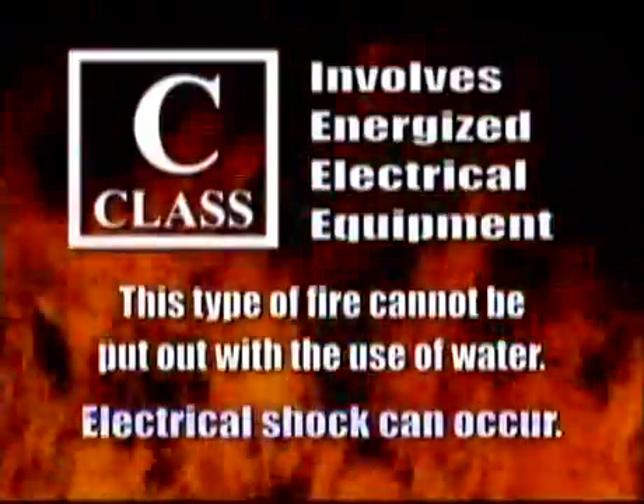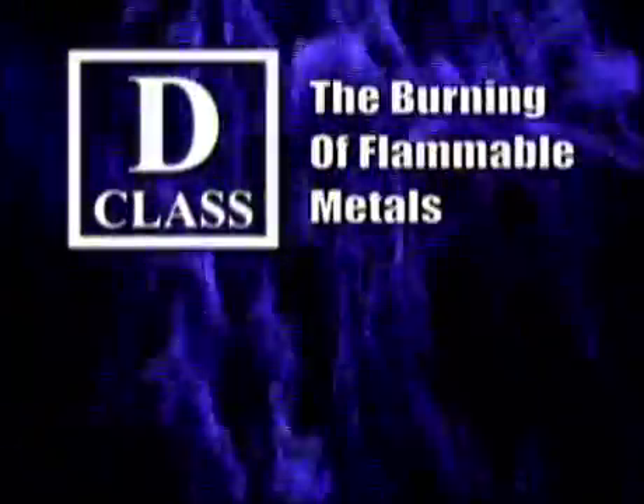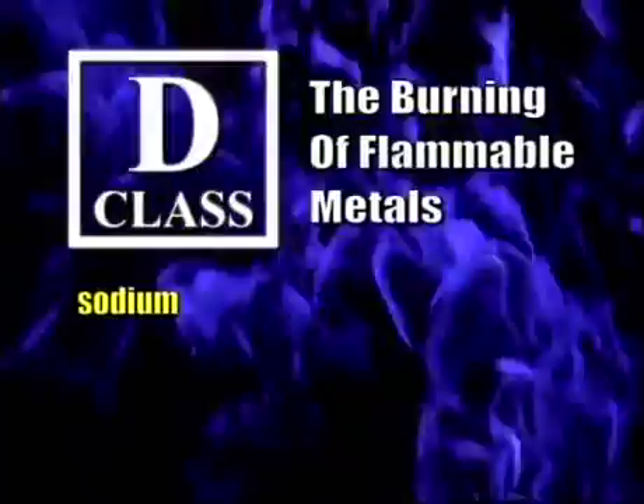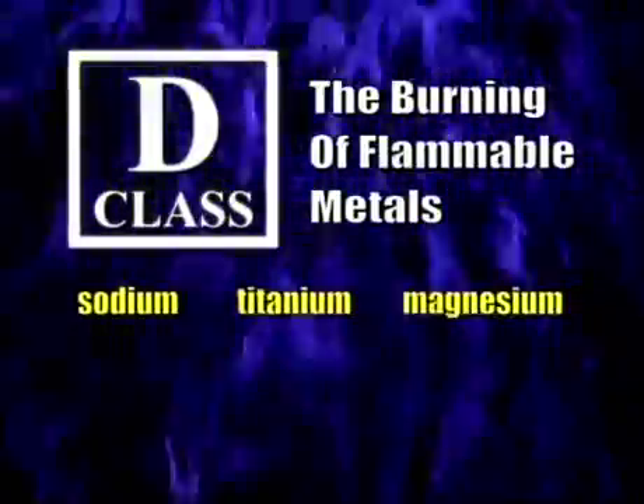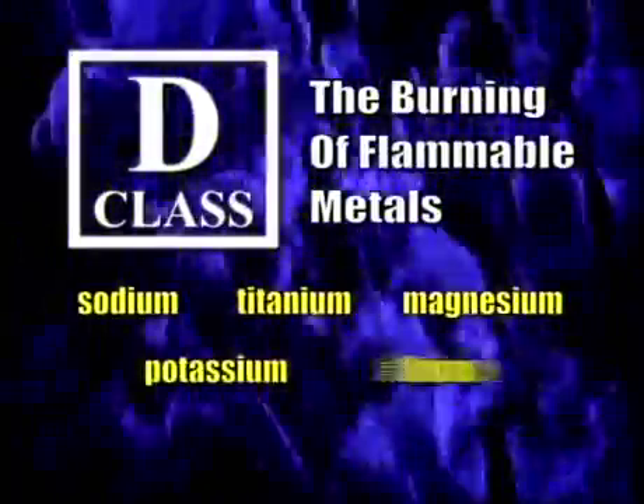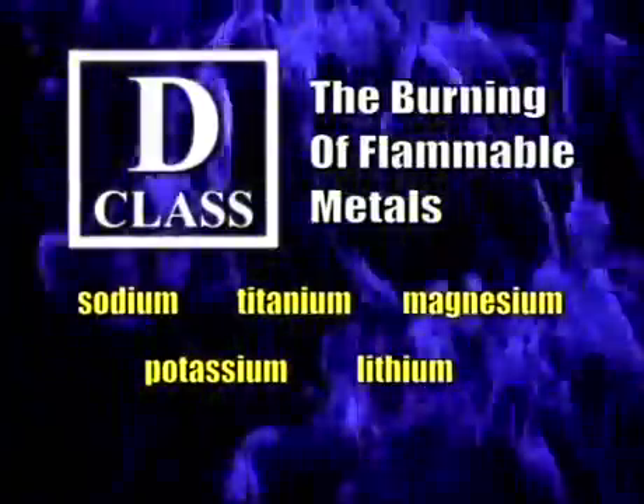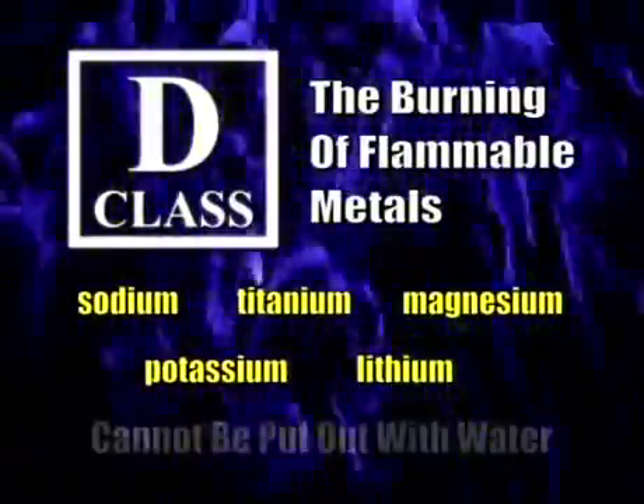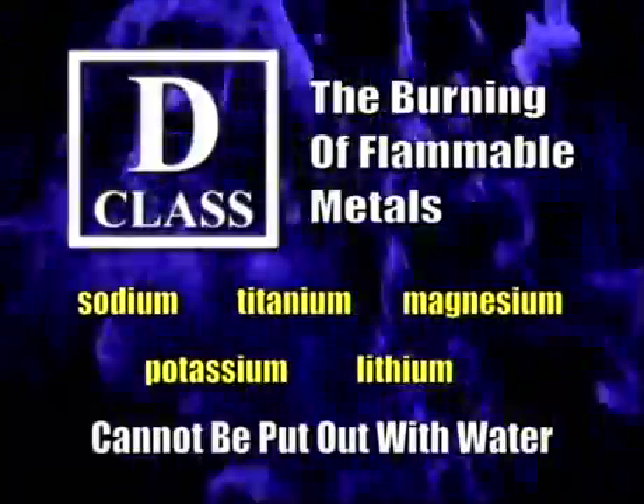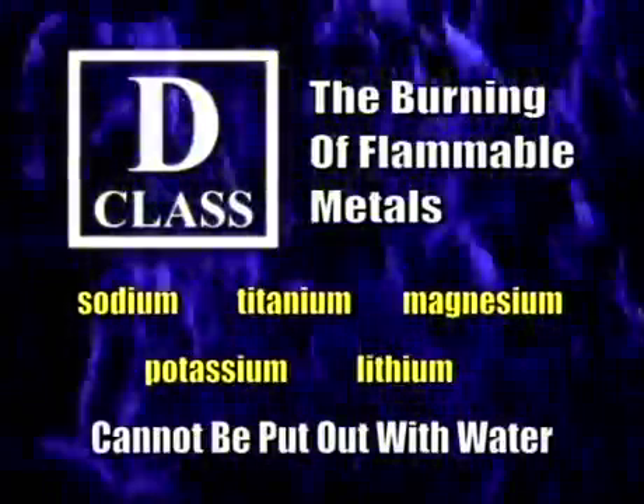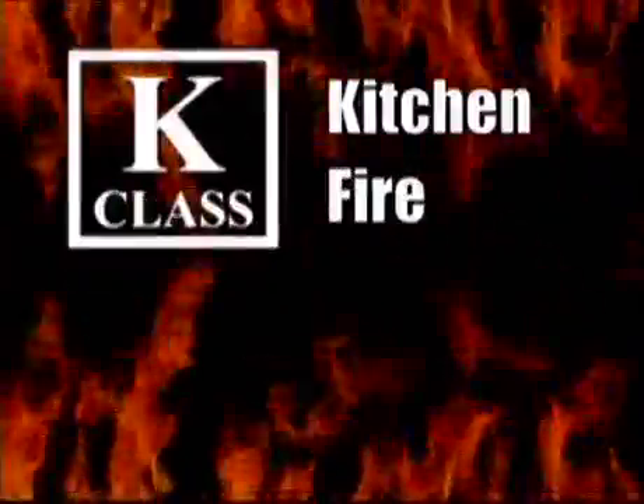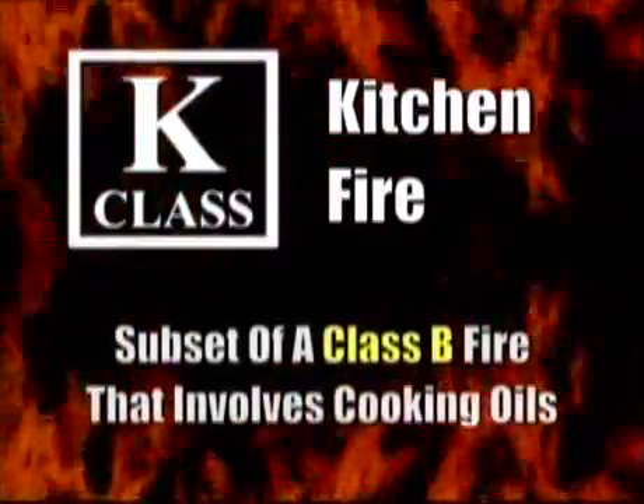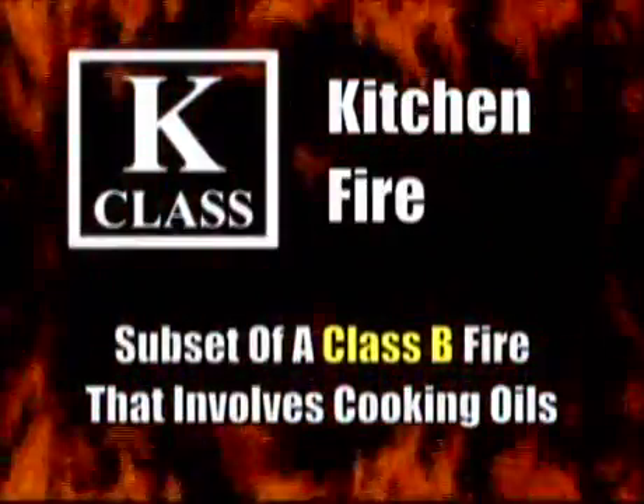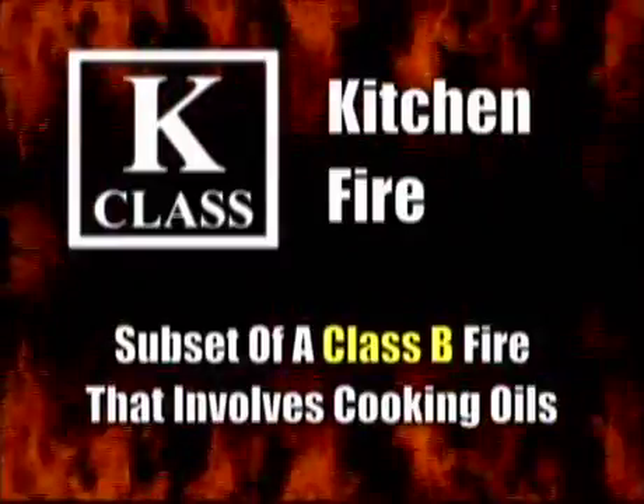Electrical shock can occur. A Class D fire is the burning of flammable metals, including sodium, titanium, magnesium, potassium, and lithium. Like a Class C fire, a Class D fire cannot be put out with water. Water can actually accelerate the fire. The last class of fire is a Class K fire. The Class K fire, or kitchen fire, is a subset of a Class B fire that involves cooking oils.